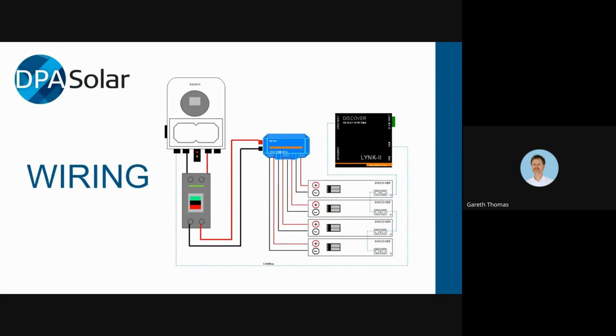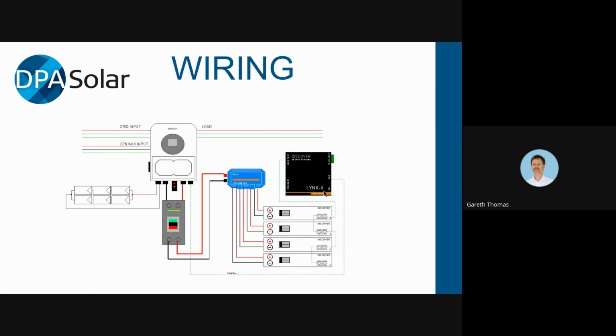In terms of the wiring, here's a nice, simple explanation of the DC wiring. This is with a Discover battery system, so that has an external BMS, like a BYD does. We've got 4 batteries going to a bus bar. This is a Lynx Power In, which is a good choice. Then going to our main isolator, and then into the Noark. And then the comms cables from the Discover batteries daisy chain together, then into the LYNK II, which is the BMS, and then from the LYNK II into the Noark. I'll show you exactly where that connects in some future slides.